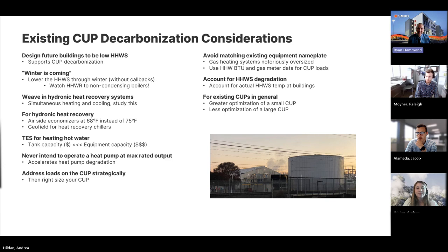Okay, so this one's a little bit thick, and I know we're running a little bit tight on time. I know there's a lot of information here. I'm going to try and get through this. What I wanted to share was some existing CUP decarbonization considerations. So you've got your existing CUP. You've designed it with extra capacity. Any future buildings you bring online, design them to be low heating hot water supply, and that will just future-proof your CUP as you further decarbonize it in the future. As other older legacy buildings come offline, you now have one less building to worry about. Winter is coming. I wish I came up with that saying. It's awesome.